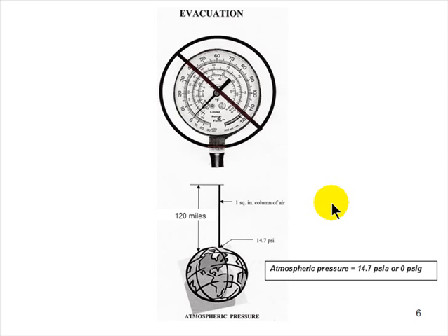If you're visiting me, and we're in the Gulf of Mexico in Tampa, standing there with our ankles in low tide, and I hand you this gauge, not connected to anything, and the gauge is not on zero, you're immediately going to stick a screwdriver in here and calibrate it till it says zero. And what you've done with that gauge not attached to anything is completely ignore 120 miles of air that weighs 14.696, 14.7 pounds. Understand that you did that.